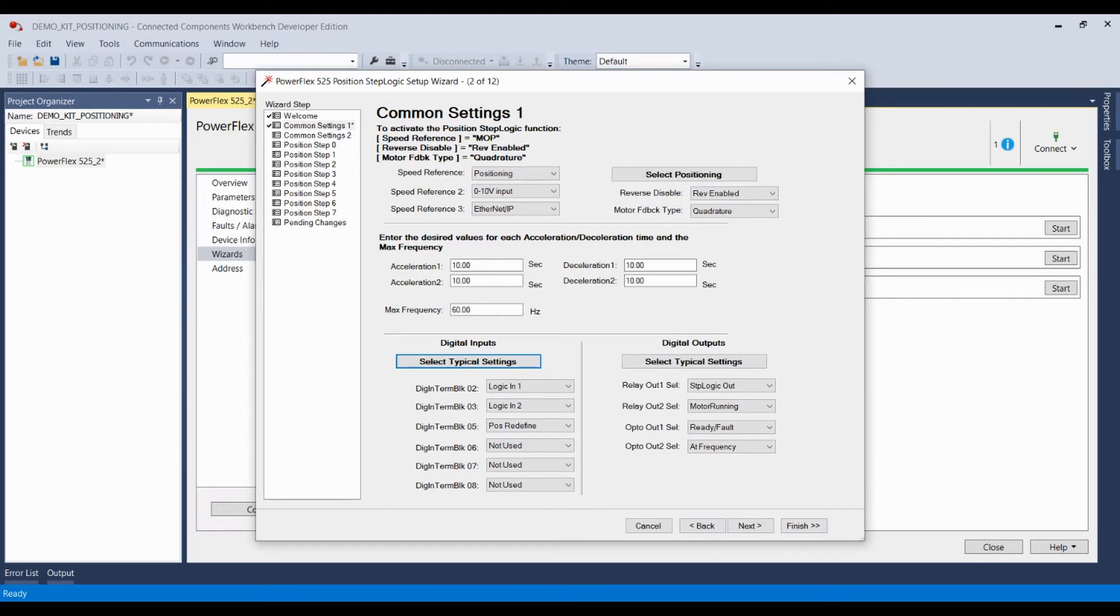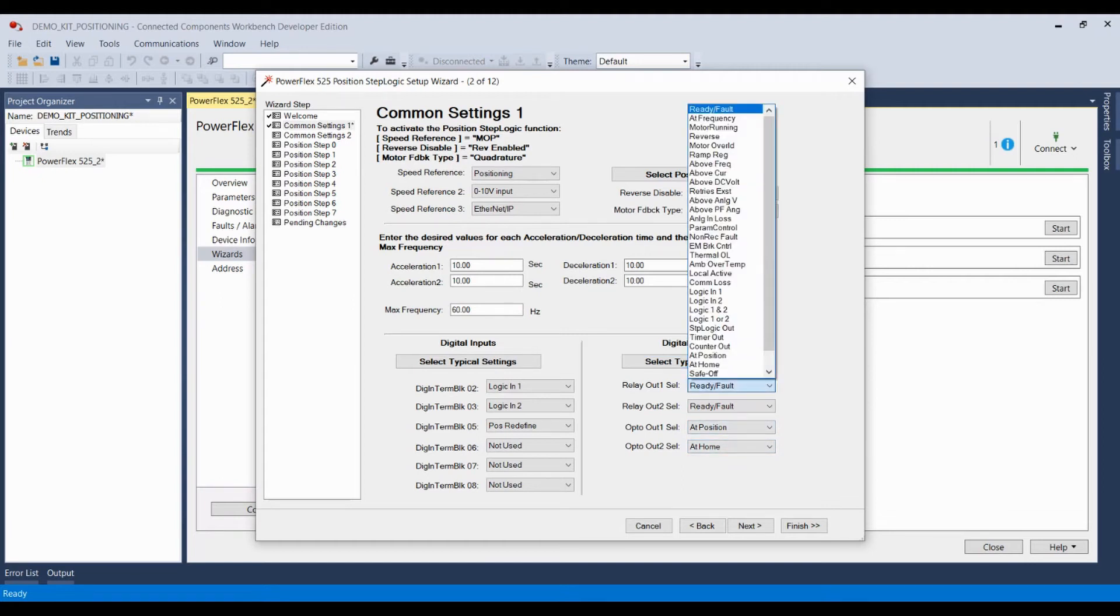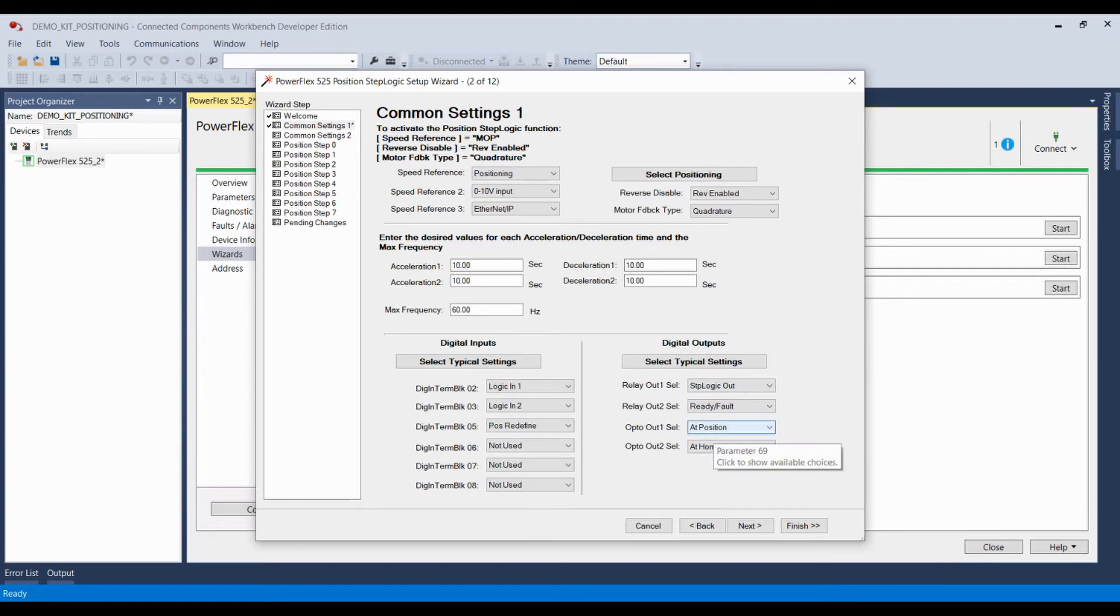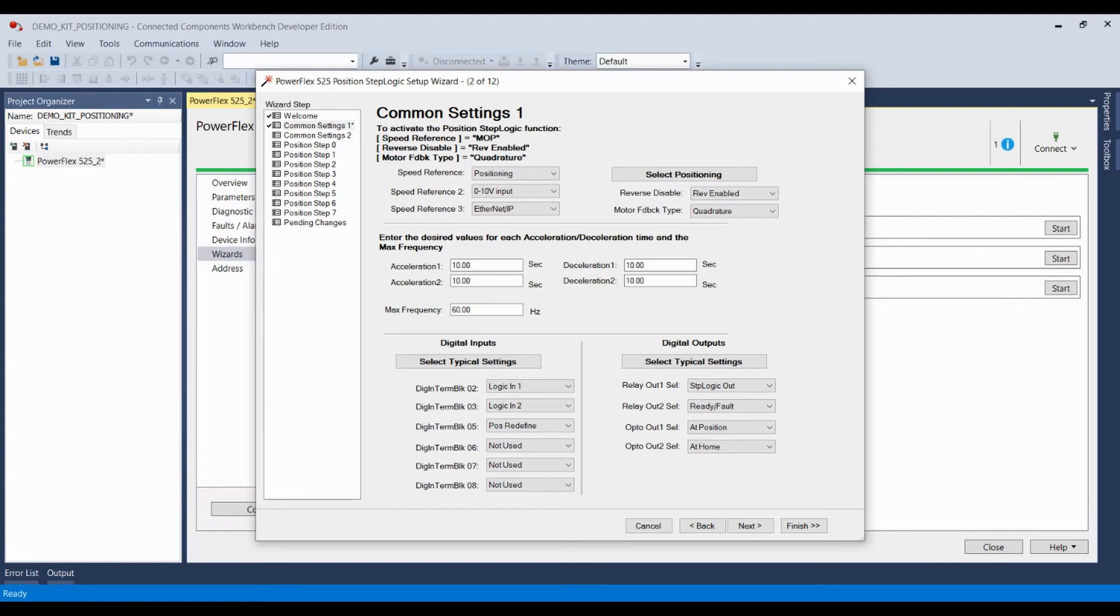And here we have our digital outputs. Our two relays for our 525 and our two opto outputs. You can also use typical settings. And this will let the system know when you're at position or at home. For this case, I'm going to make relay out one, let's see, step logic out. And I'm going to keep these as is. Now, if you're using absolute positioning or even incremental, once you've reached your position, opto out one would then send a signal out to the system, letting you know you're in position. And that can be used to coordinate activities with the drive's position. In this case, I'm going to make relay out one, step logic out. Now, what this means is when a particular position has been reached or has been completed, this particular relay will be set to the on position. And that can be used to send a signal to the rest of the system to let them know that the receptacle is in place.